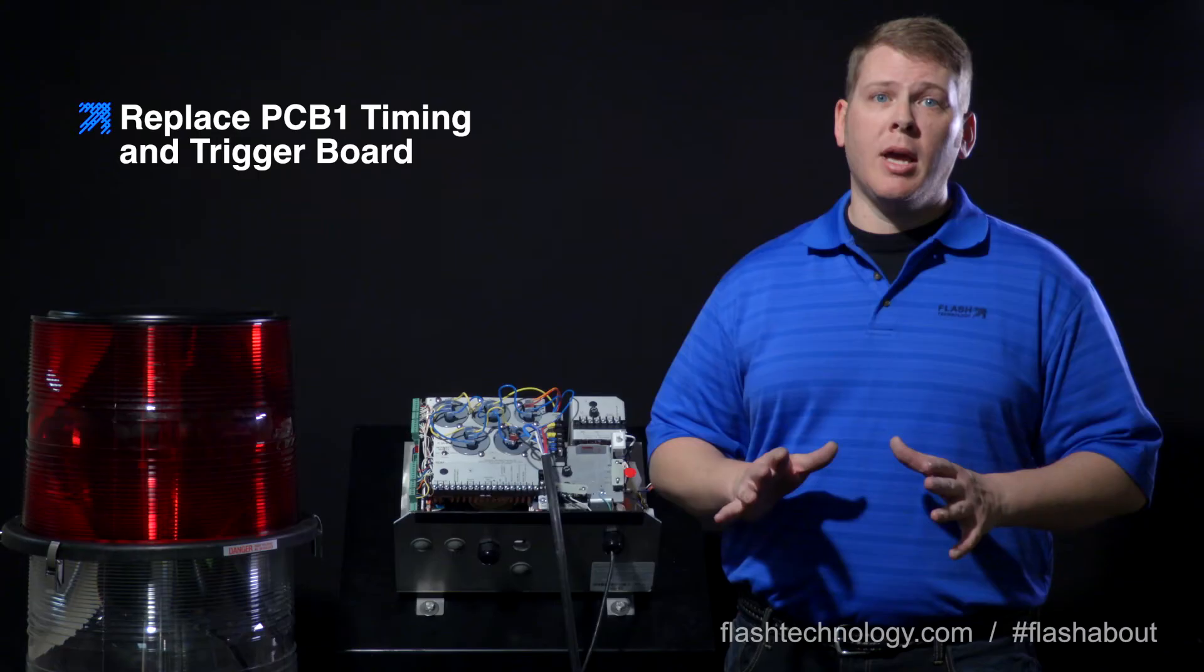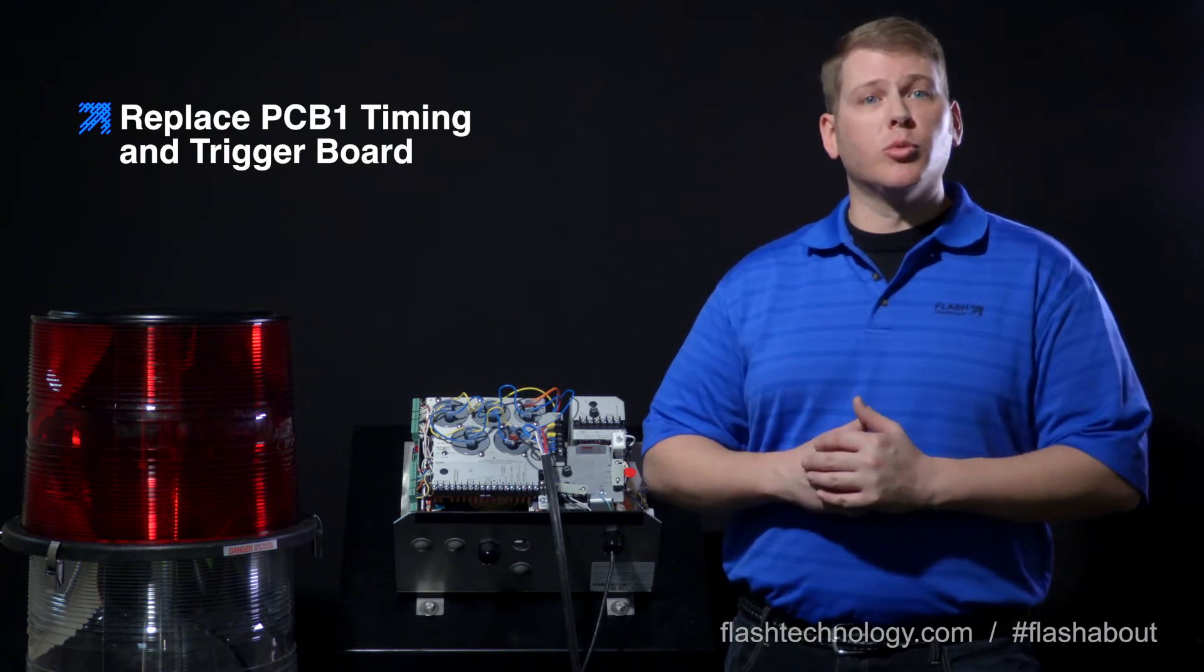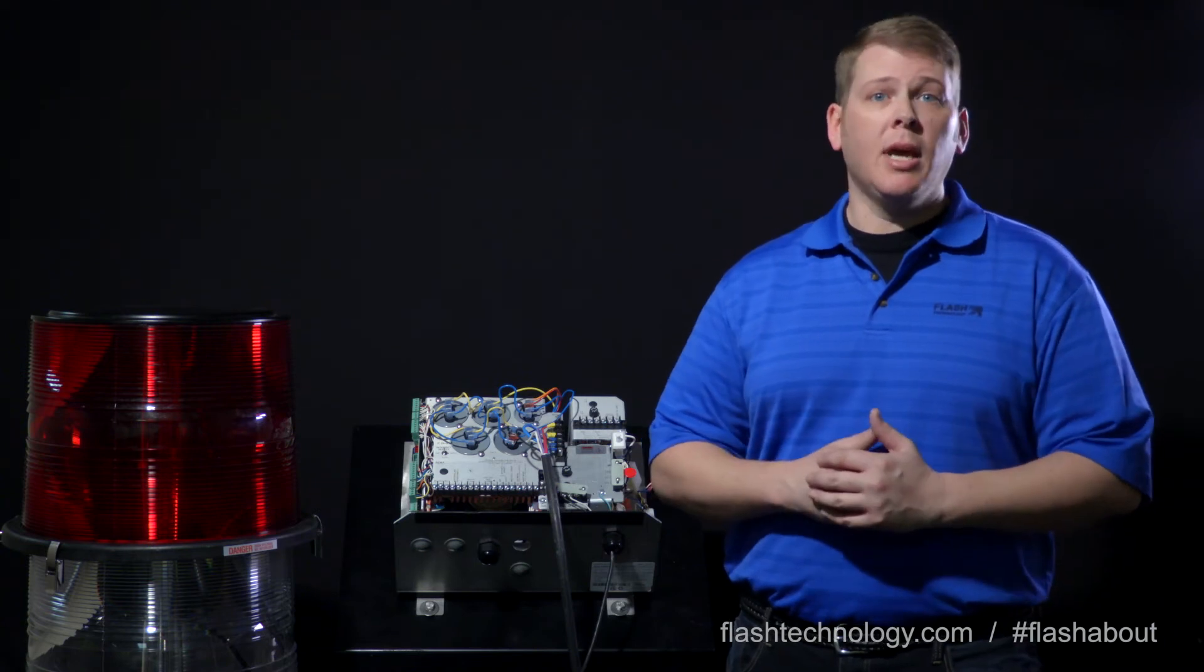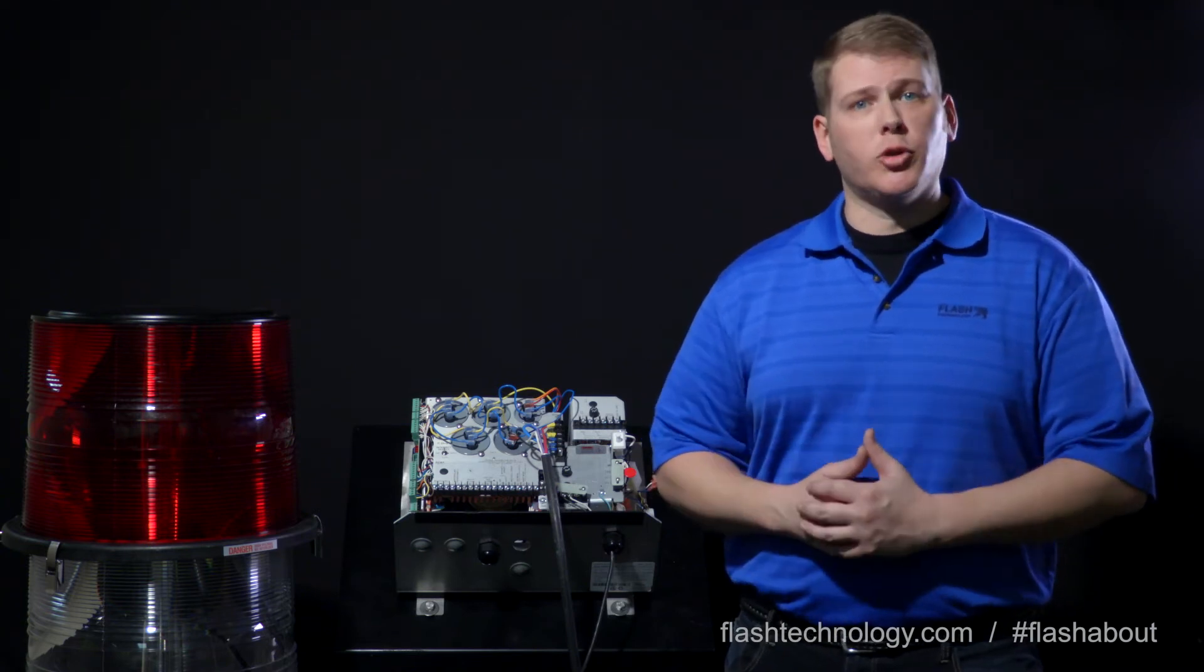If the voltage is approximately 100 volts DC but the system is not operating properly, you will likely need to replace the board to resolve the trigger issue. However, if the voltage is below 100 volts DC, we'll need to take a look at the source of the trigger voltage on the T1 power transformer.